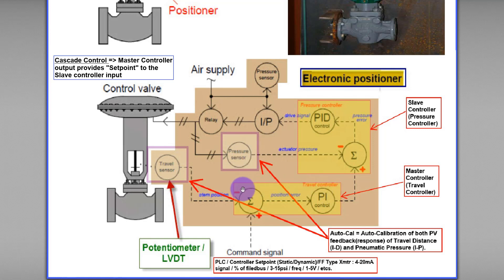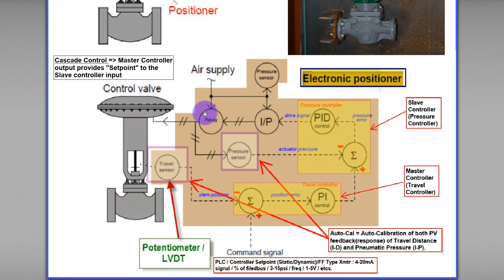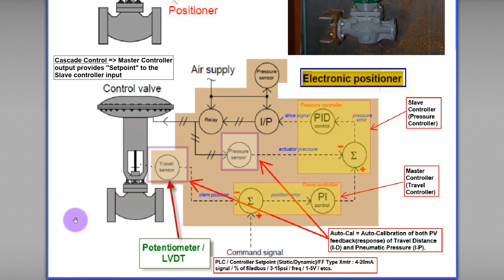In this electronic positioner, the travel controller is the master controller, and the pressure controller is the slave controller. As we know, a controller requires two inputs: one is the set point or command signal, which is given by another controller such as a PLC or DCS.